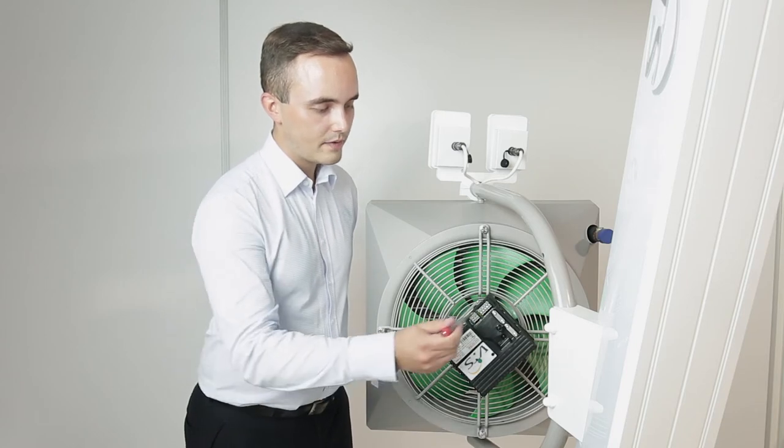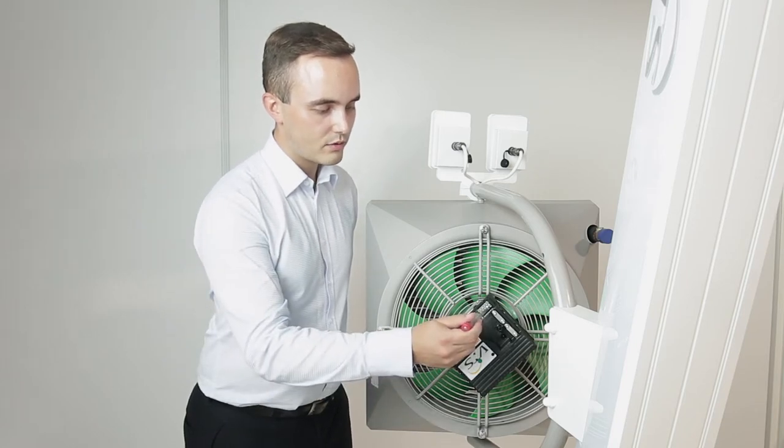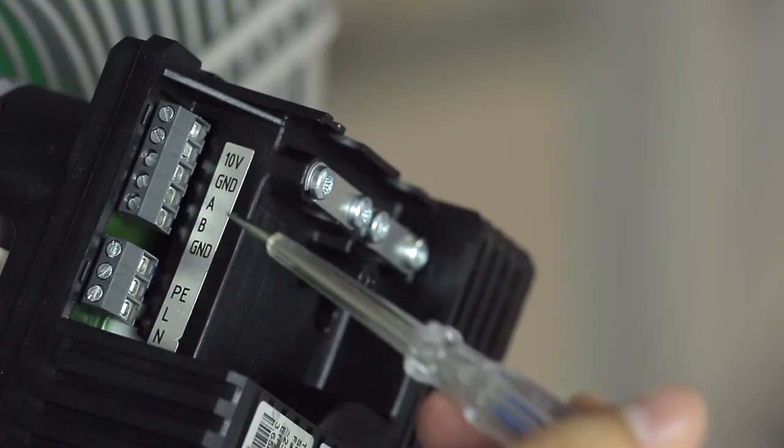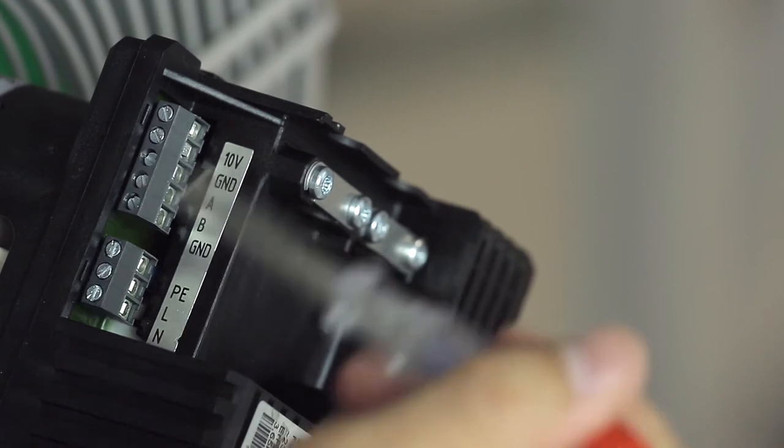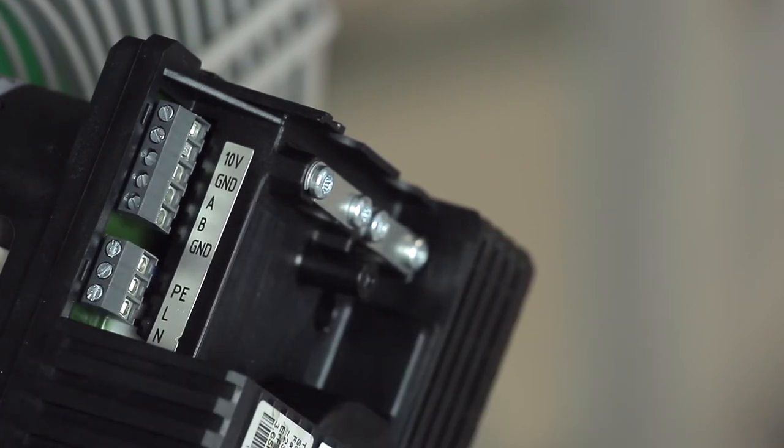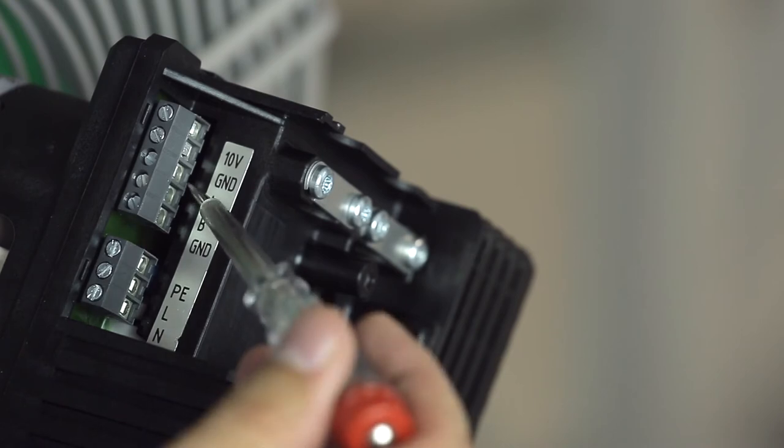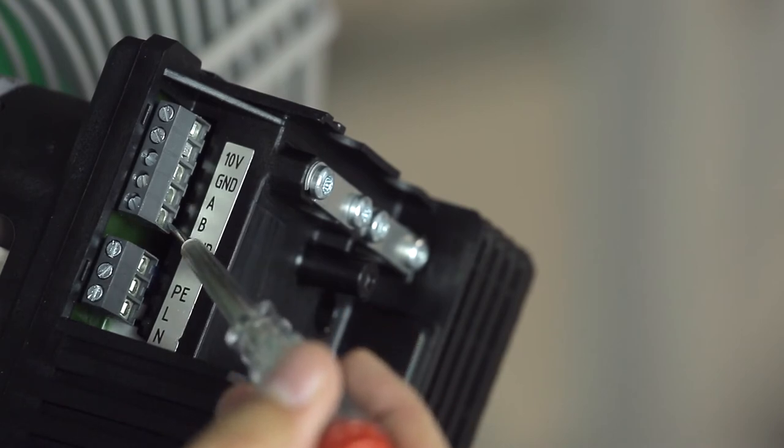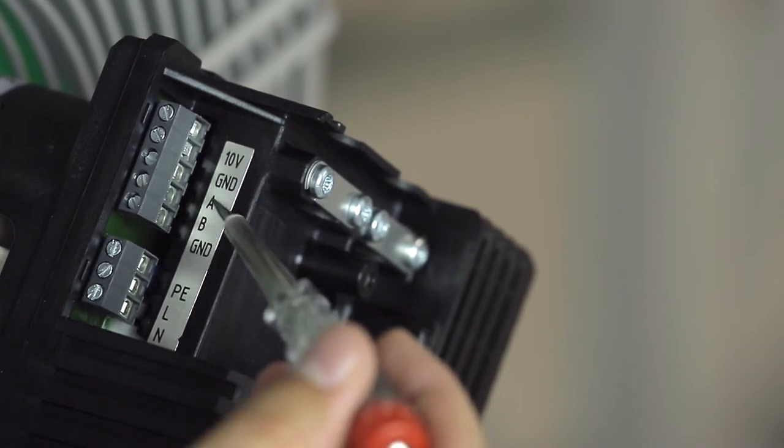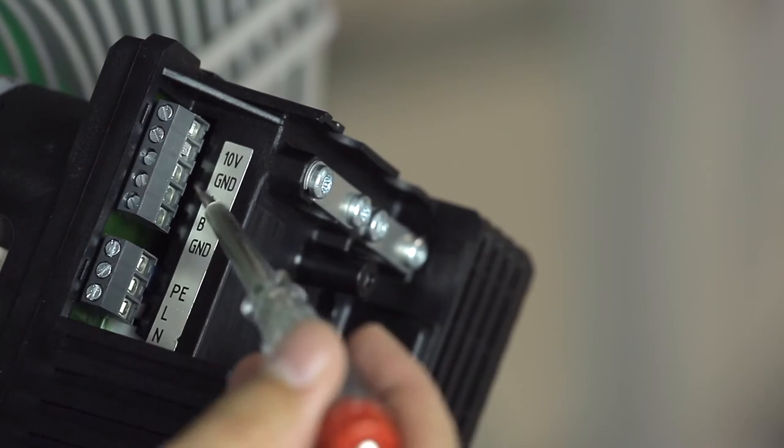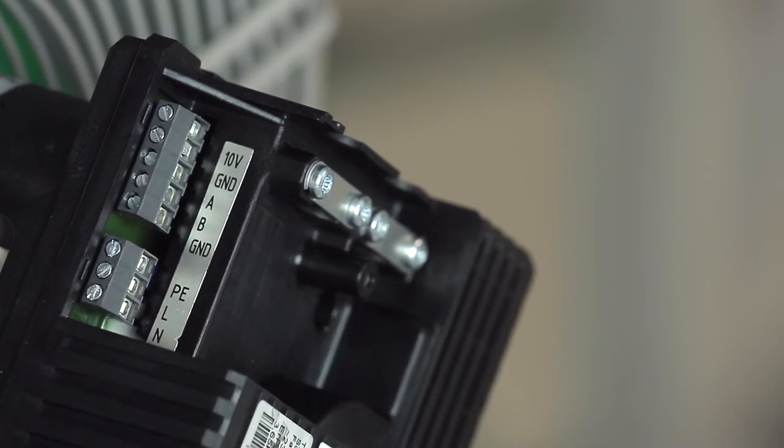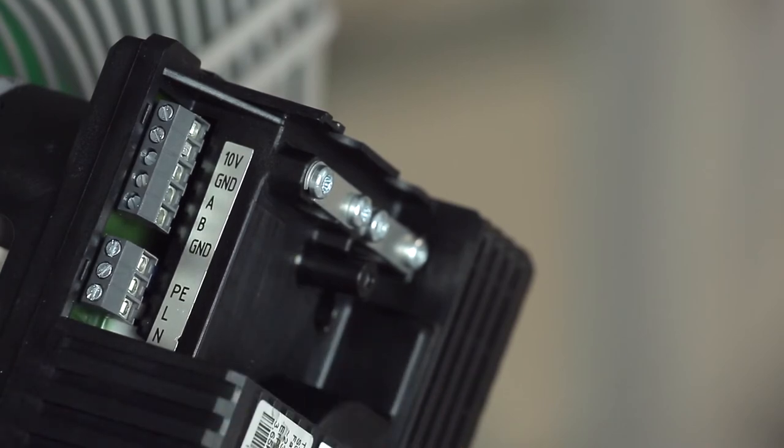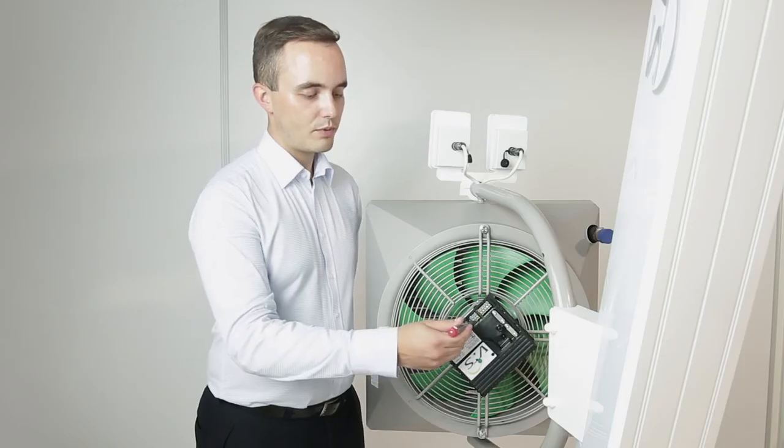To control the motors RPM, connect a 0-10 volt wire and a ground wire for this connection. Inputs A, B, and GND give us direct connection to the external BMS system, which is made possible by using the Modbus RTU protocol.